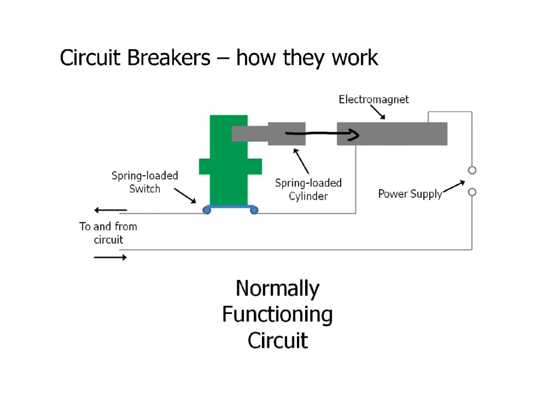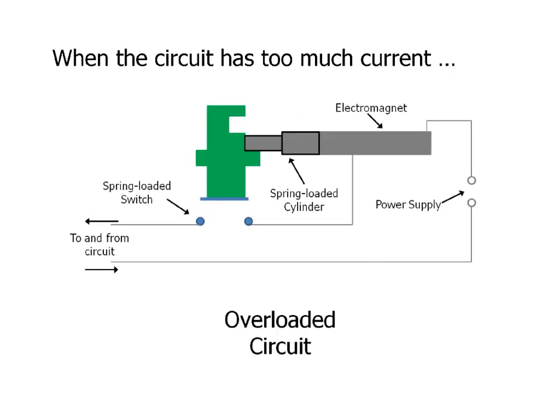So let's look at how that looks after it's been tripped. Same basic idea, but now the cylinder has been attracted to the electromagnet. The whole switch apparatus has popped up because it's spring-loaded, opening the switch, so current has stopped, and the cylinder is holding this open. It's sprung open and won't close again. Everything is locked in this situation.